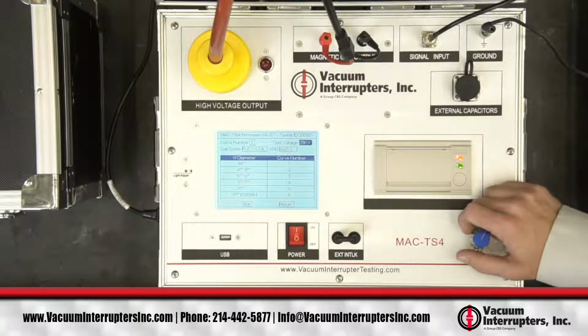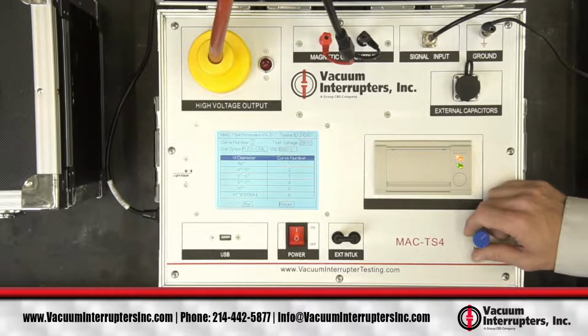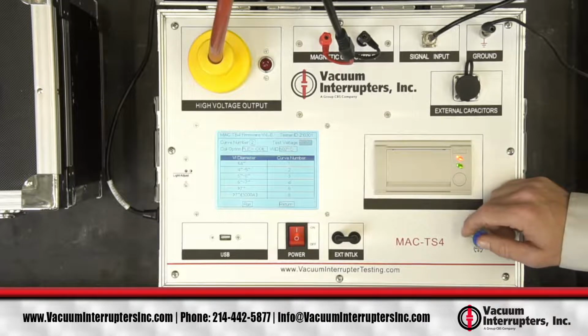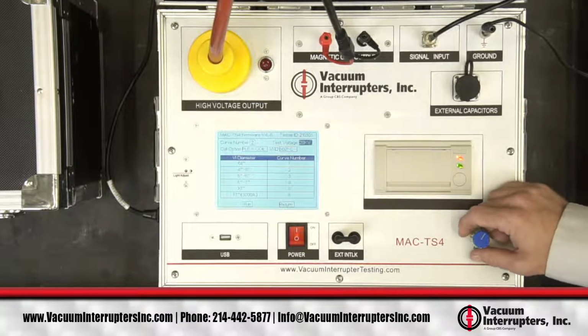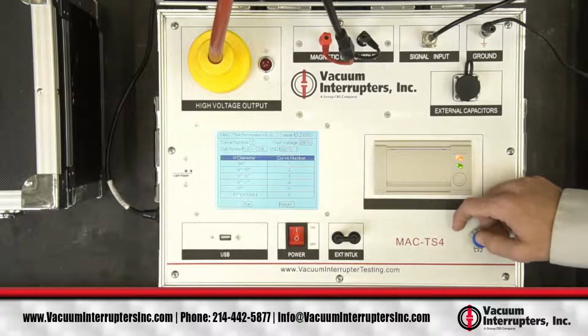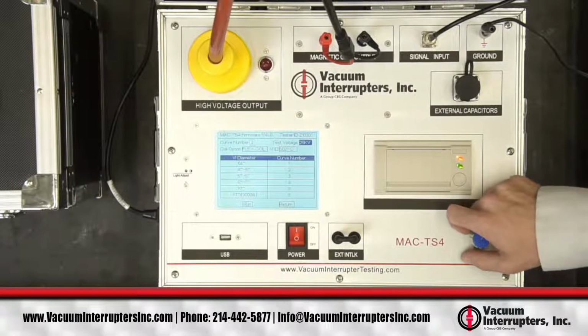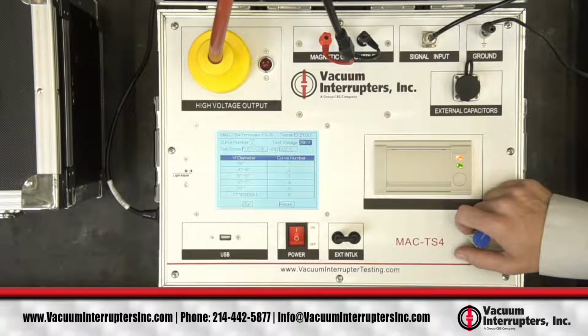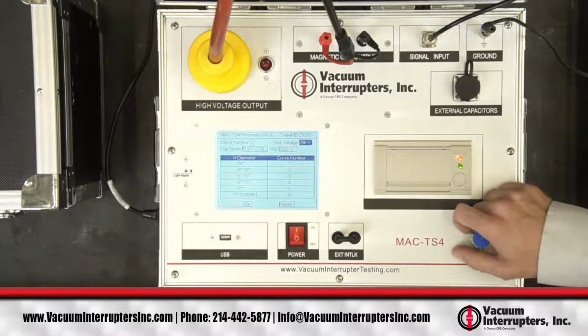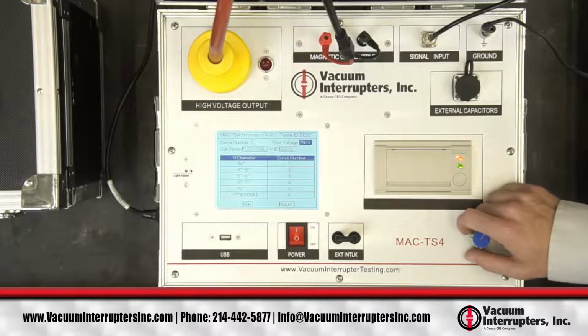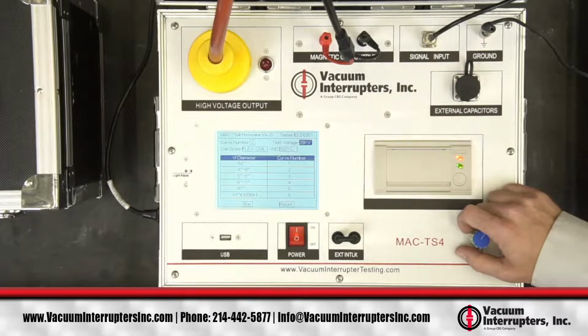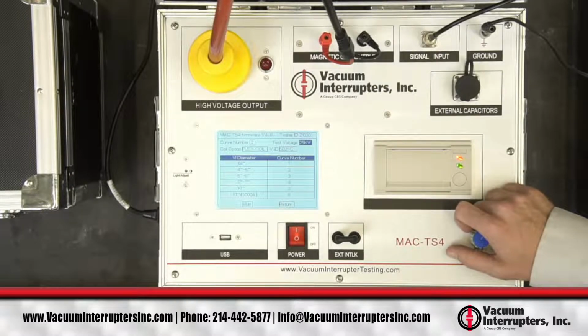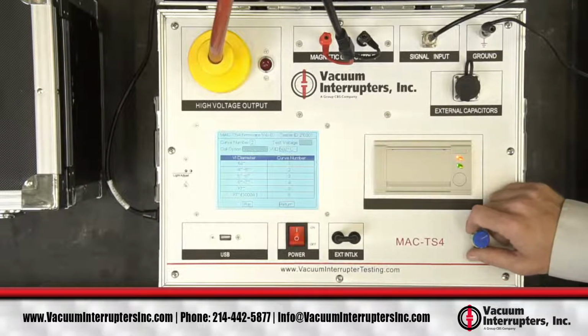You've got 2 different test voltages here. You've got 25 kV and you've got 12 kV. Just as a rule of thumb, you use 25 kV for anything that has a contact gap greater than 1/4 inch, 12 kV for anything less than 1/4 inch, which generally means that breaker bottles will use the 25 kV and contactor bottles will use 12 kV setting. There are some unique breaker bottles that are much shorter than others, which you would use the 12 kV setting, but those are pretty rare.